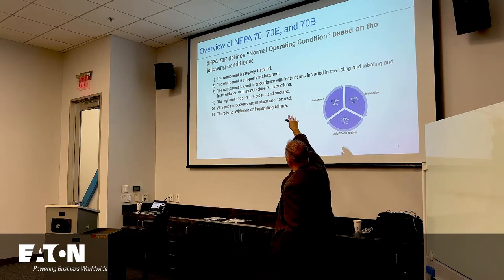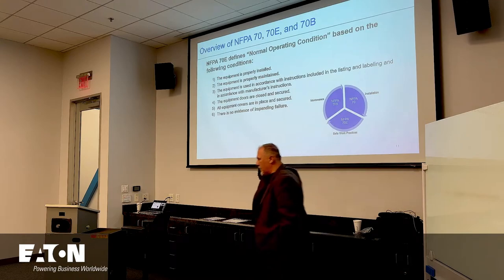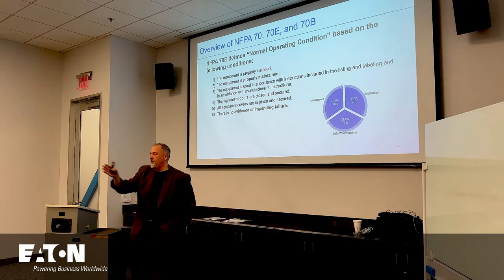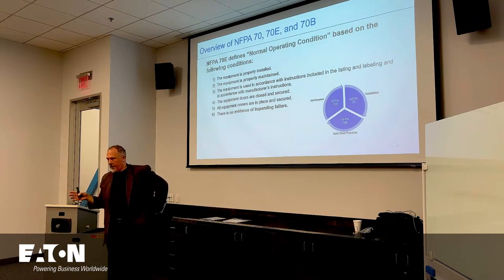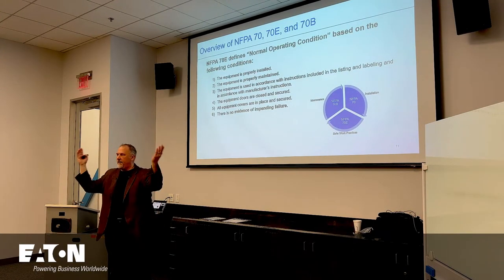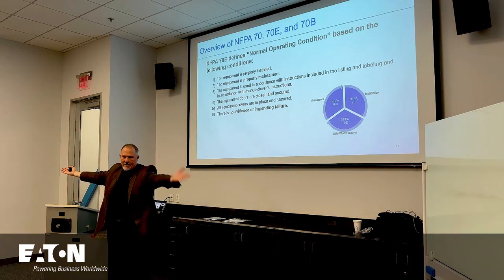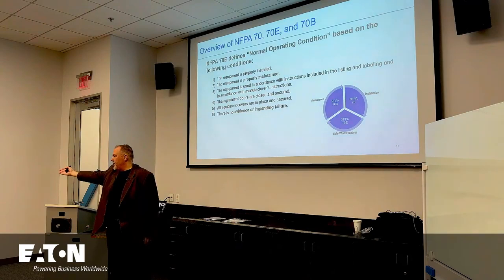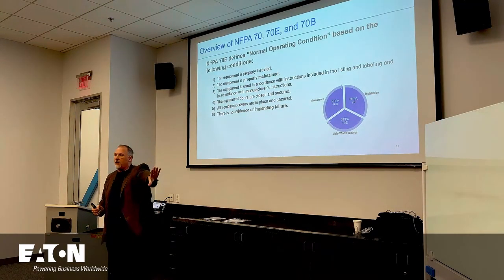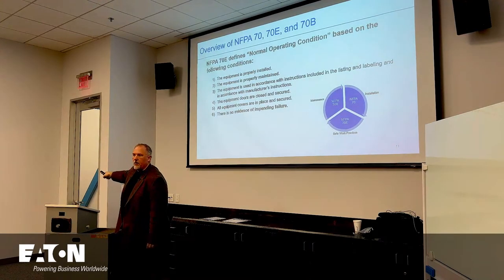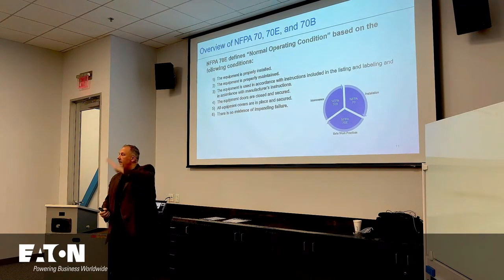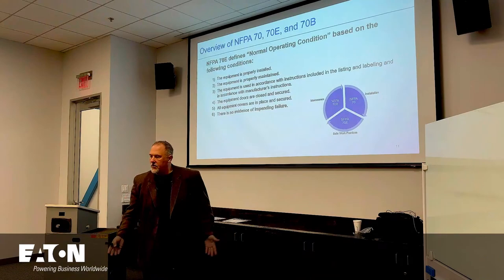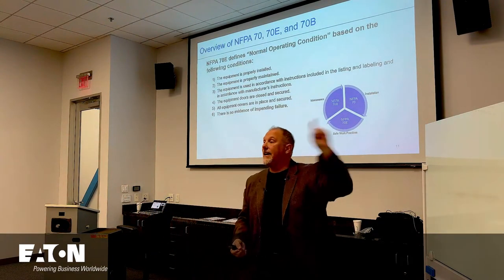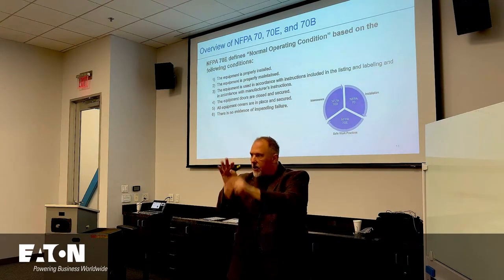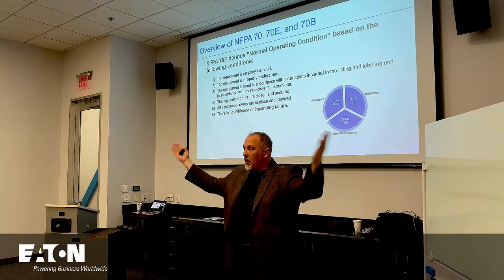What we do in 70E tells you about your normal operating condition. Why is that important? There are some individuals, you'll have this side of the room and that side of the room. This side says if there's a panel board on the wall, you can't walk in that door without wearing PPE because it's an energy source. The other side says I can walk into this room without PPE, and I can even take the cover off as long as I'm not trying to do something. So you have both perspectives.